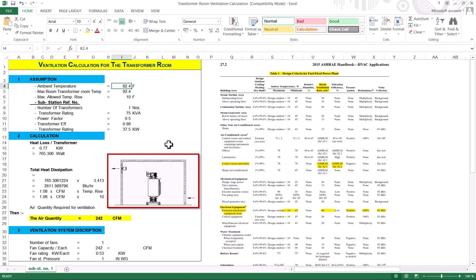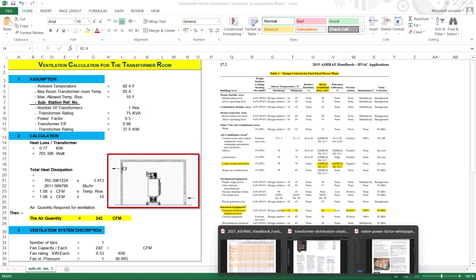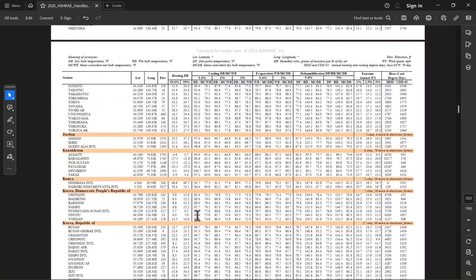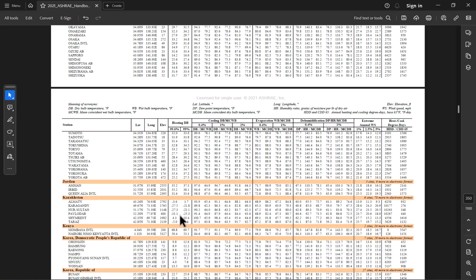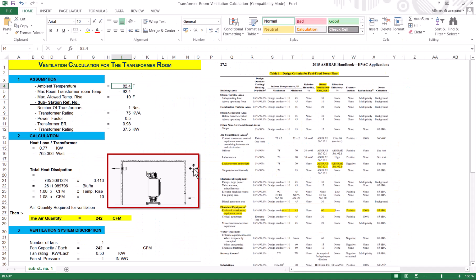You can get this ambient temperature from the ASHRAE temperature data — there are a lot of countries and cities listed, and I will share these files so you can download and use them. Now, the second thing is the maximum room temperature in the transformer room. The temperature should not exceed the ambient temperature plus 10 degrees — so if it's 100°F ambient, the maximum room temperature will be 110°F, if 120°F ambient, then 130°F.